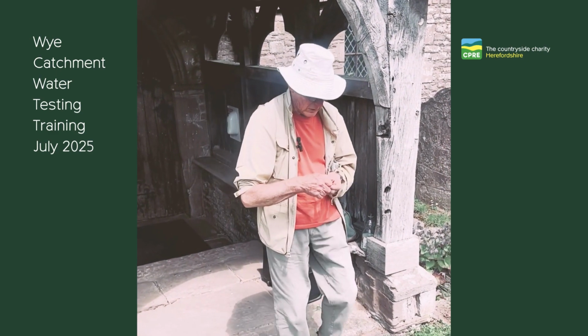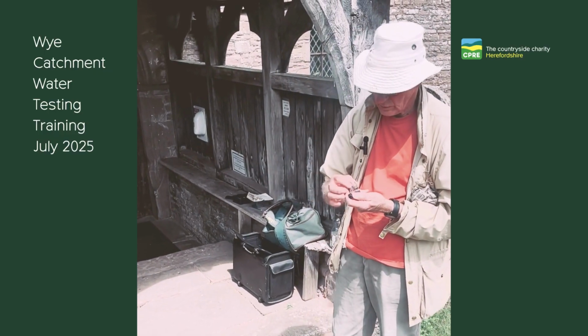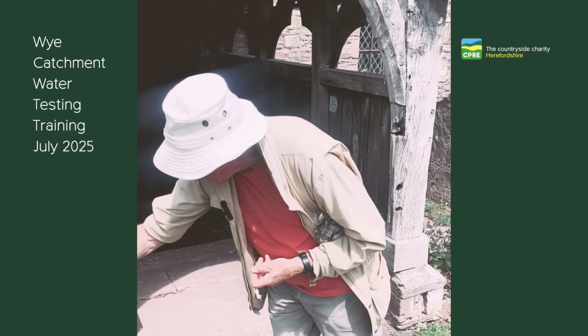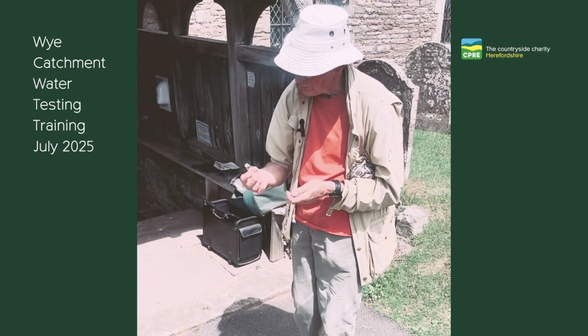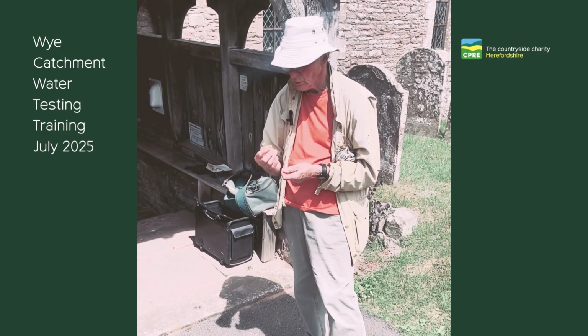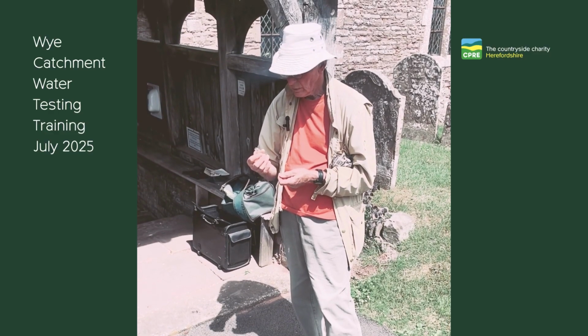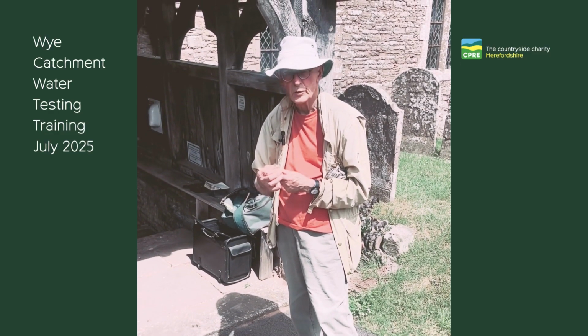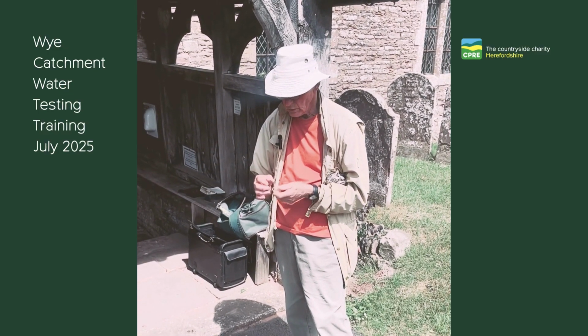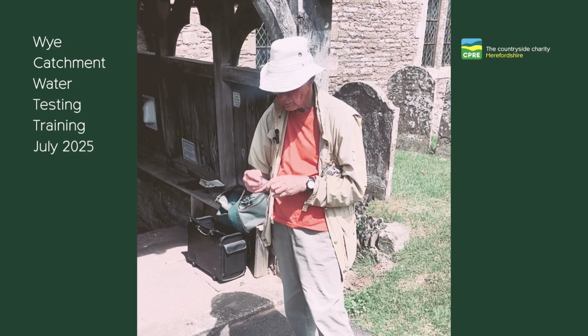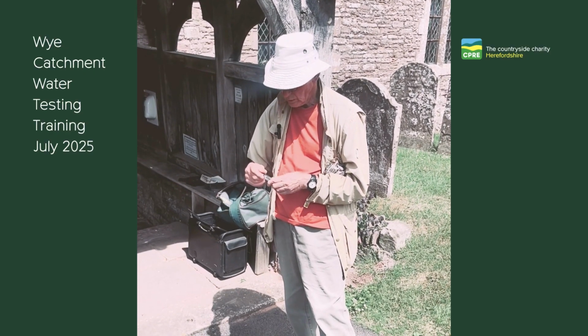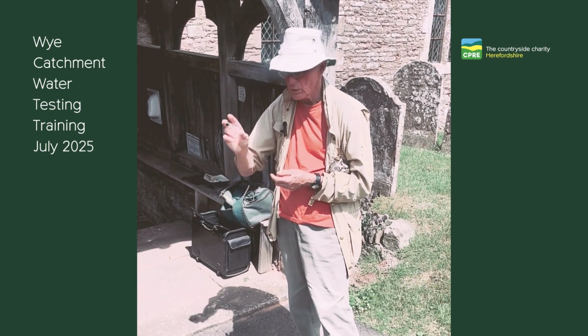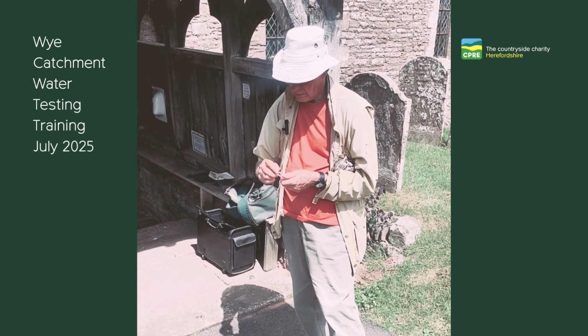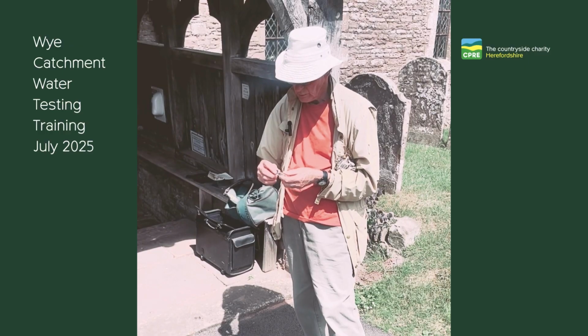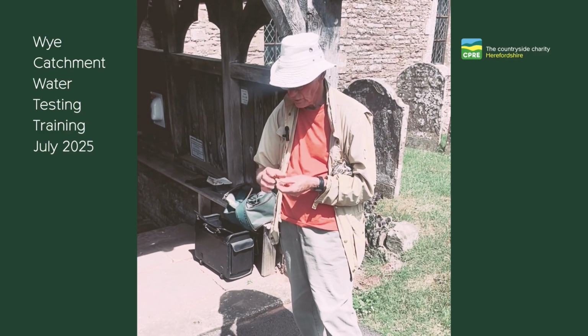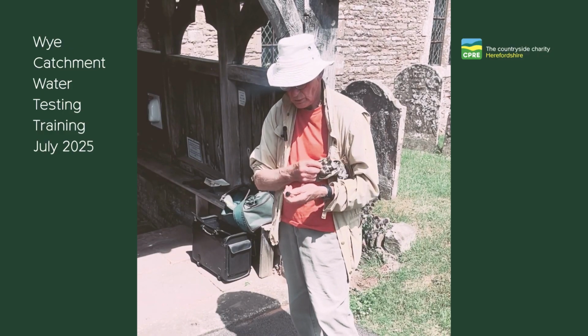In the interest of not making this presentation too long and boring, I haven't washed anything very thoroughly, but ideally before using your cuvette, any cuvette, you should wash it out 3 times using water from the stream that you're sampling.